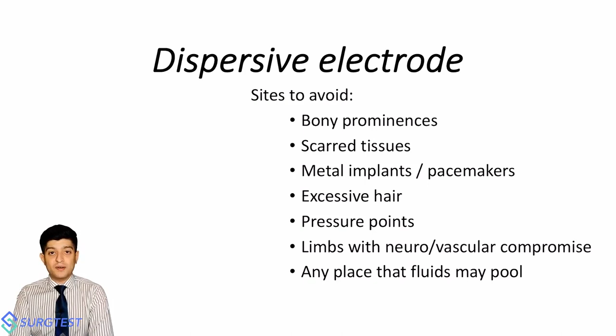Do not apply the dispersive electrode at any place where fluids may end up pooling, because that pooling, especially if it's spirit, can be the point at which a fire may begin and a patient may get badly burned. Additionally, the fluid acts as a low resistance conductor of electricity, and patients can end up having an odd burn even beyond the dispersive electrode.